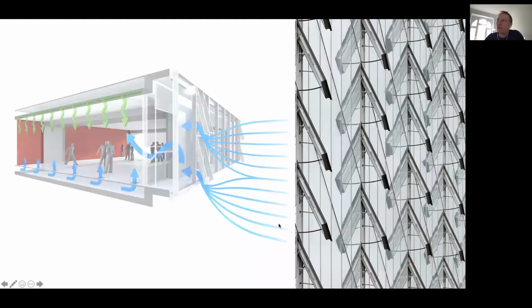To the east and west, we have a double facade. The main reason is to get the shading device—a retractable Venetian blind—outside the conditioned environment, into this facade cavity. As a byproduct, we have operable windows, unusual in this extreme cold climate. We control the outer openings so we can dissipate the heat that piles up in the facade cavity in summertime to the outside.